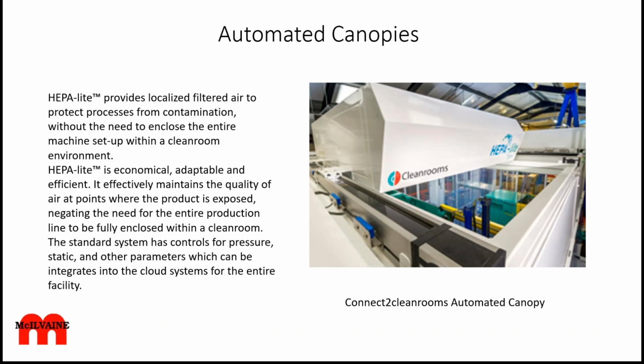The provision of air at different locations at different times offers a whole new dimension. Connect 2 Cleanrooms actually has the HEPA-lite, a mobile canopy which provides air downward only in the area that's needed. It's economical and adaptable, maintaining air quality at points where the product is exposed, negating the need for the entire production line to be fully enclosed within a clean room.